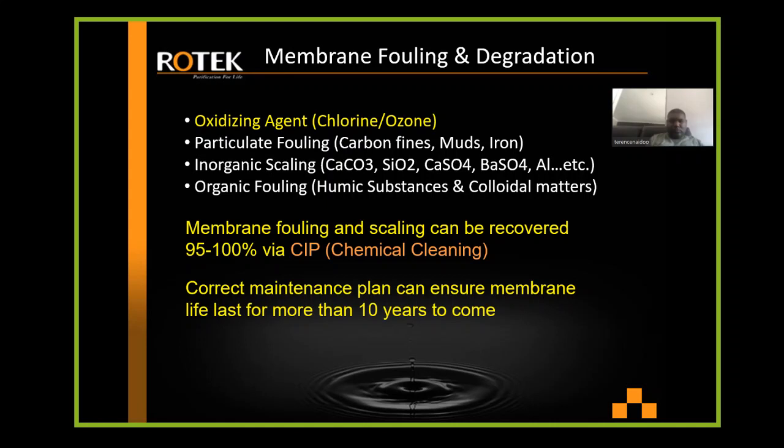or even sometimes less. And remember this: if you don't recover the membrane 100%, that means there is some old scale still on the surface of the membrane, and that old scale is a very good foundation for new scale to build up on. Understand? Yes. Okay, so if the old scale isn't removed completely, after the CIP the membrane will foul more quickly after the first CIP attempt.